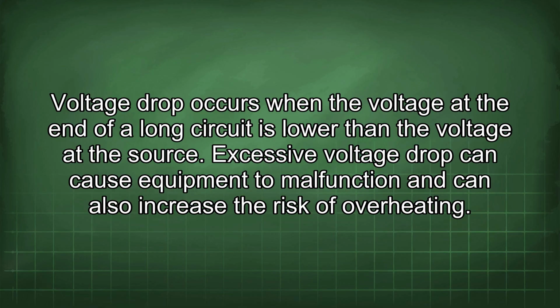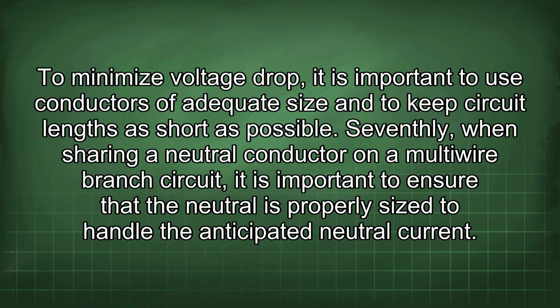Excessive voltage drop can cause equipment to malfunction and can also increase the risk of overheating. To minimize voltage drop, it is important to use conductors of adequate size and to keep circuit lengths as short as possible. Seventhly, when sharing a neutral conductor on a multi-wire branch circuit, it is important to ensure that the neutral is properly sized to handle the anticipated neutral current.